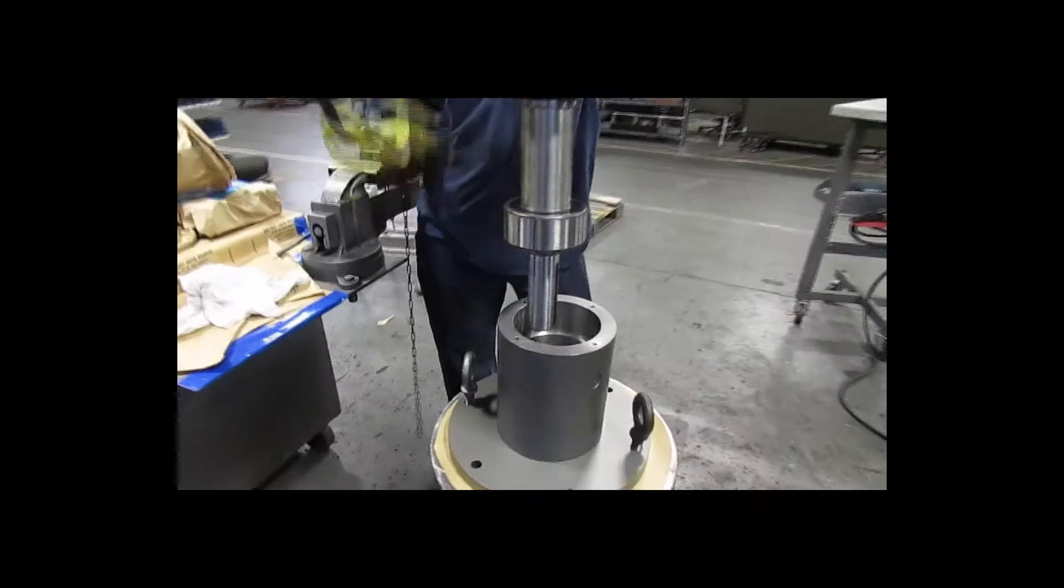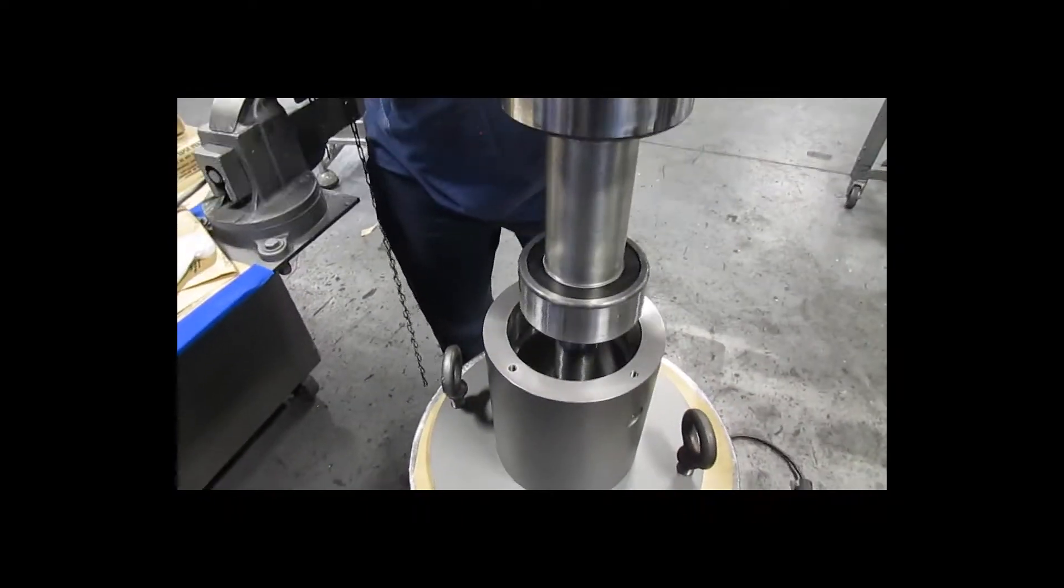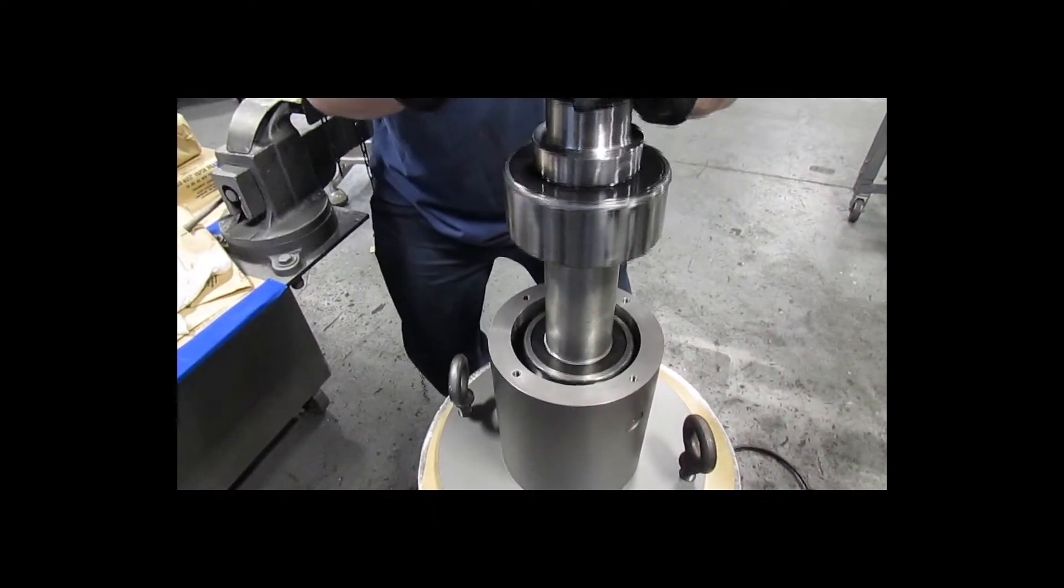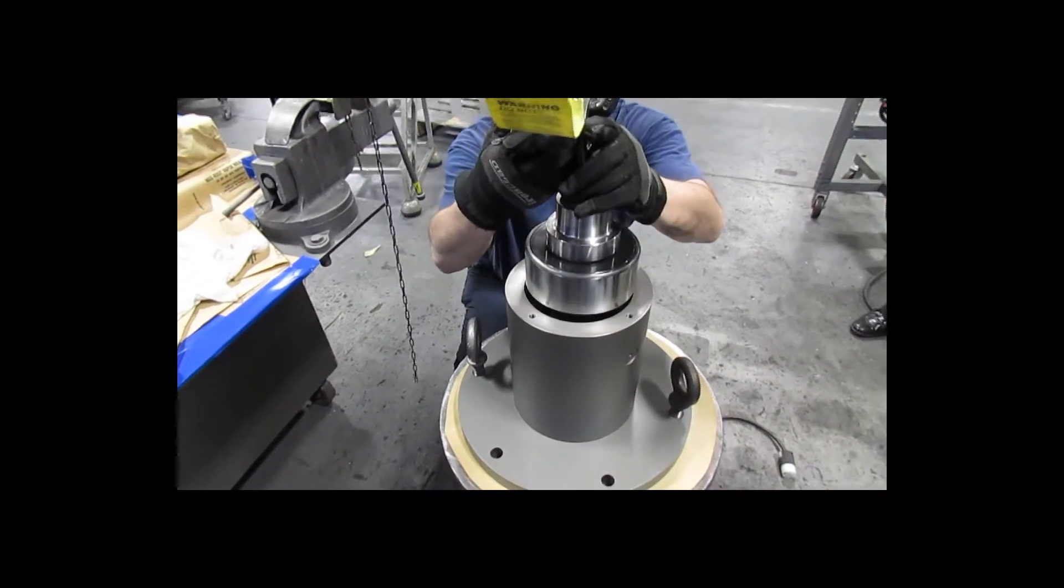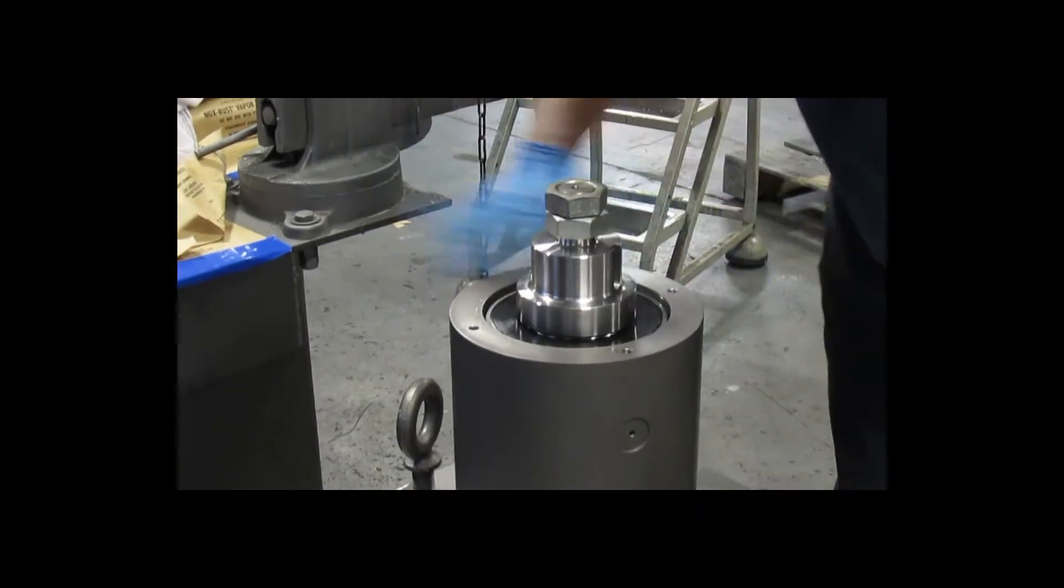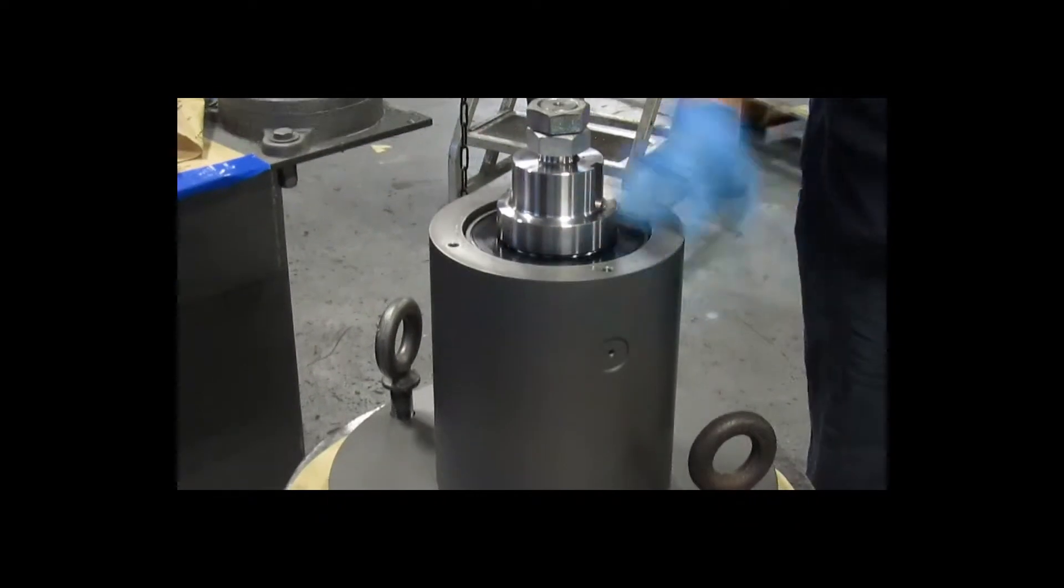It's also important to keep the shaft straight so that the bearings do not get cocked once they enter the housing. If the shaft is straight, the bearing should slide in without too much resistance, after which time the upper rotor bearing seats against the shoulder.